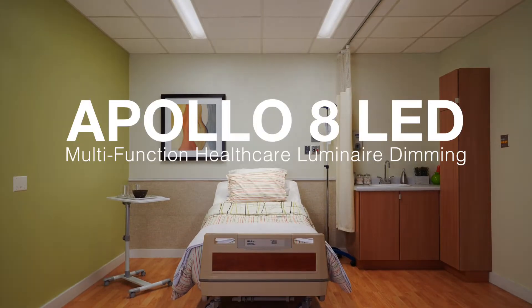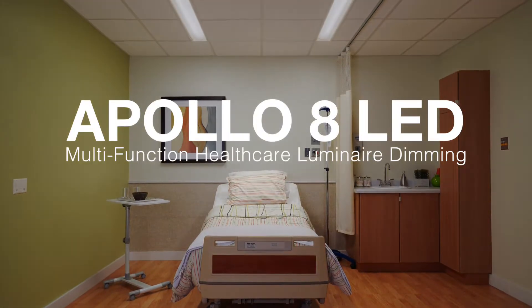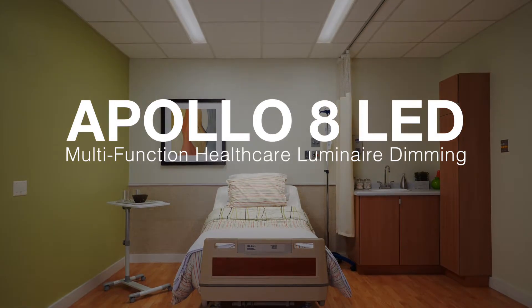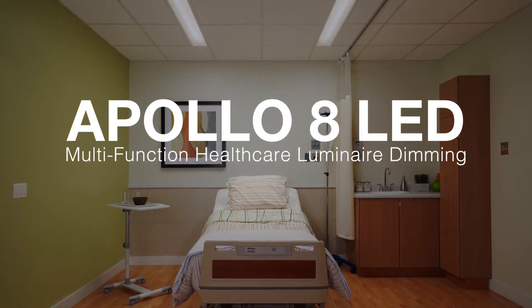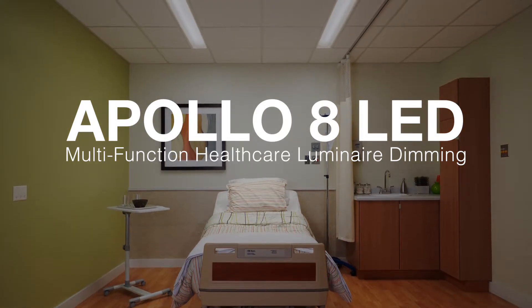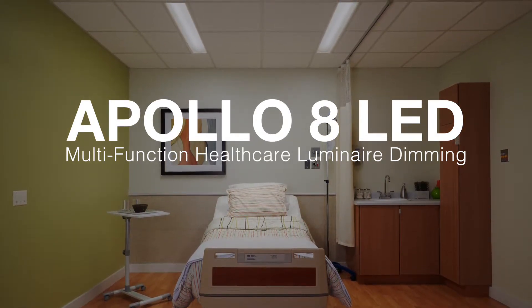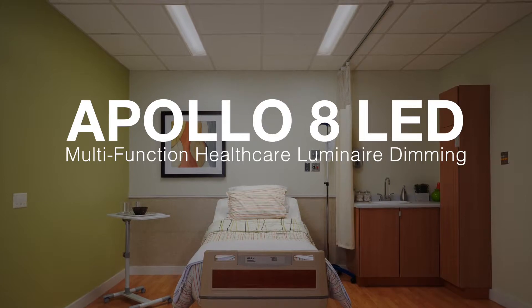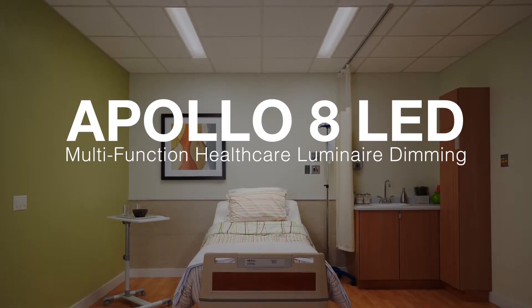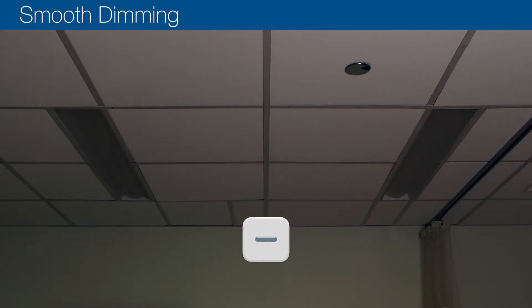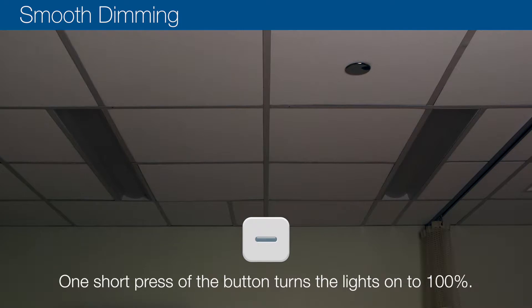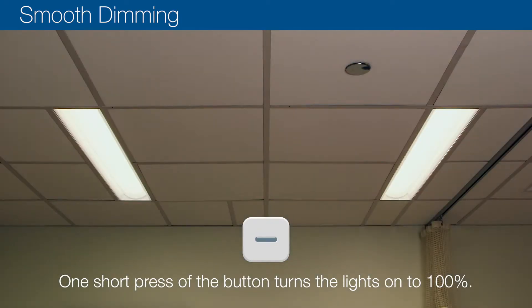Apollo 8 LED provides on/off, smooth, and step dimming options with the use of a low voltage controller and 0-10 volt dimming drivers. Smooth dimming using the low voltage controller: one short press of the button turns the lights on to 100%.